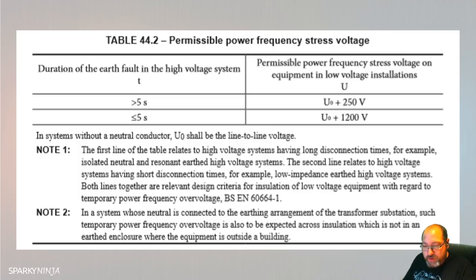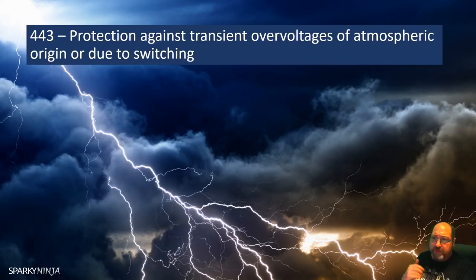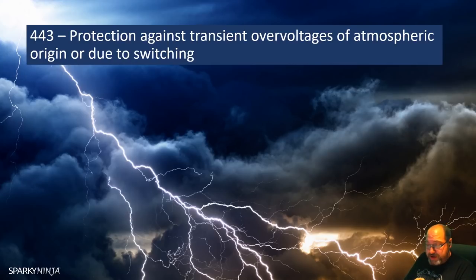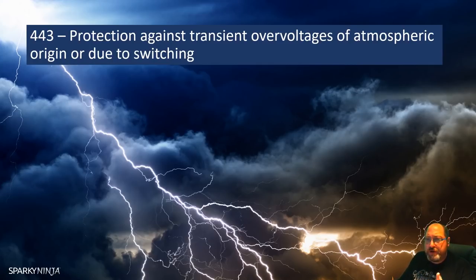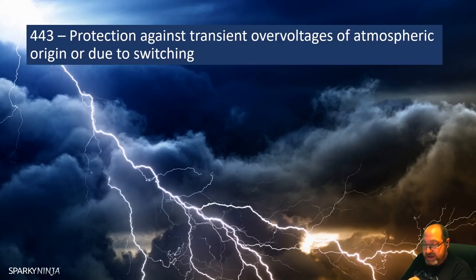Moving on to atmospheric origin — instead of the high voltage fault problems, let's discuss protection against transient overvoltages of atmospheric origin or due to switching. In the 18th edition they've rewritten this with a completely different risk assessment method approach. This section deals with the protection of electrical installations against transient overvoltages of atmospheric origin — such as lightning strokes — which are transmitted by the supply distribution systems including direct strikes, and against switching overvoltages generated by equipment in the installation.